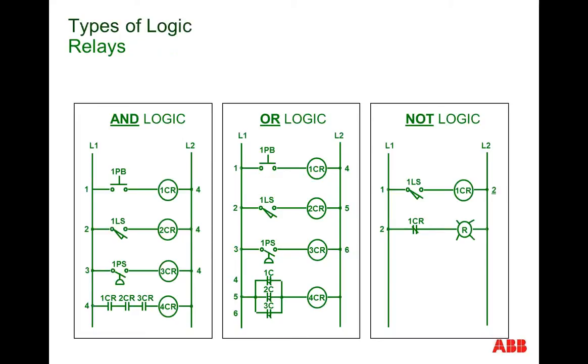Now, let's look at these various forms of logic, and logic is shown here. If push button 1, controlling this relay, and limit switch 1, controlling this relay, and pressure switch 1 are closed, you'll see in series those contacts associated with those coils are wired in series. So my AND logic says this and that will turn on that. The other form of logic is OR logic. This button, this limit switch, this pressure switch, any of them, this one or that one close, I'm going to close control relay number 4. There's even something called NOT logic. If limit switch 1 closes and fires the control relay number 1, the normally closed contact is going to open up, turning off the red pilot light.